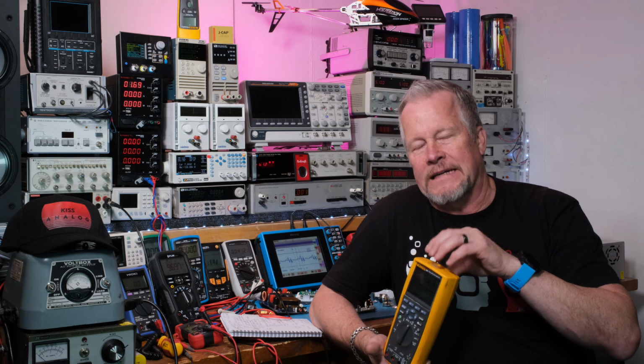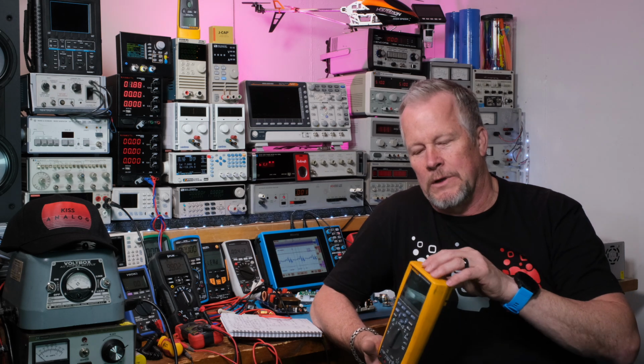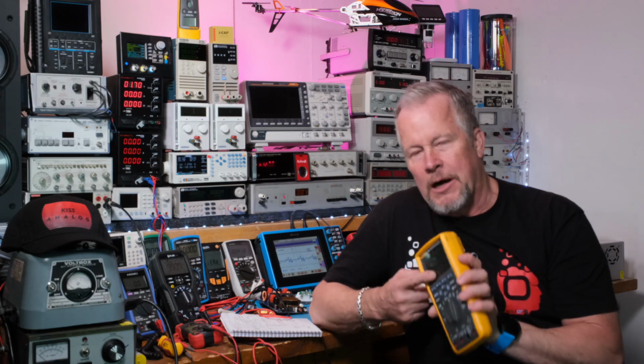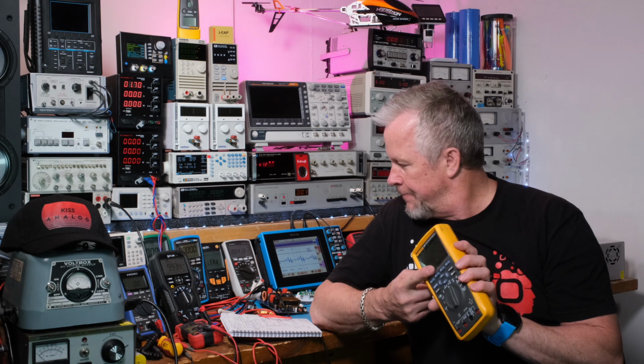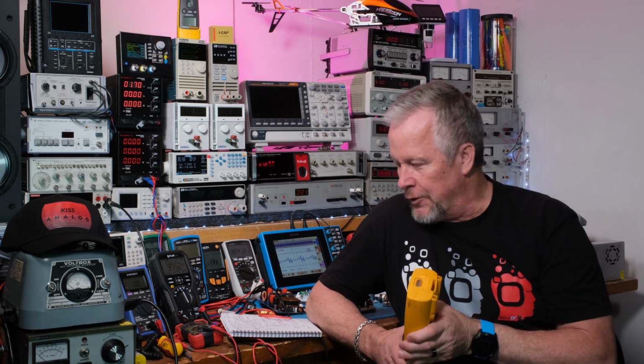high-end meters are fast. They update 5 times a second. That's really fast. Most meters are like 2 times, maybe 3 times a second. The bar graph, is it 30? I think it's 30 times a second. The Keysight was confusing because it had a fast and a slow mode. The fast mode was 40 times a second, and the slow mode was 5 times a second. So it didn't differentiate between the bar graph and the display, and I'm a little thrown off there. I'm not sure, but it's at least as good as the Fluke. It's actually faster, 40 times versus 30.